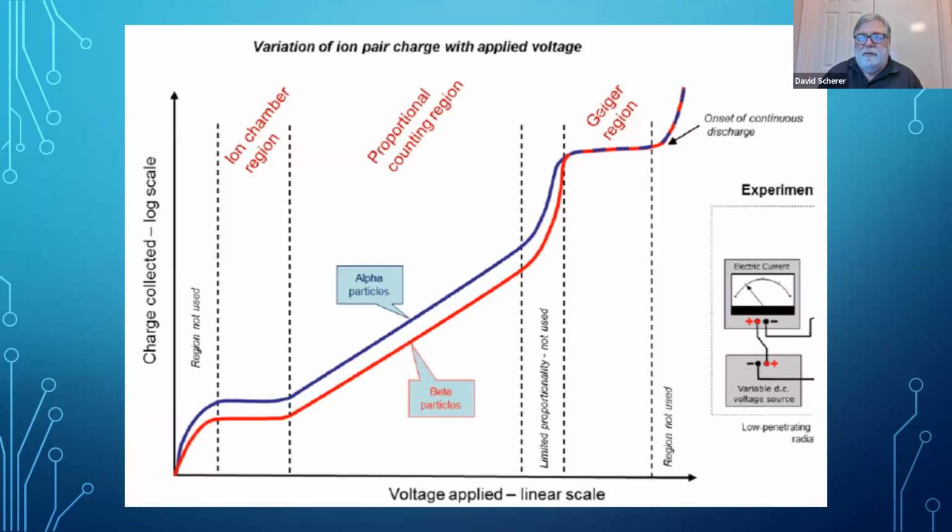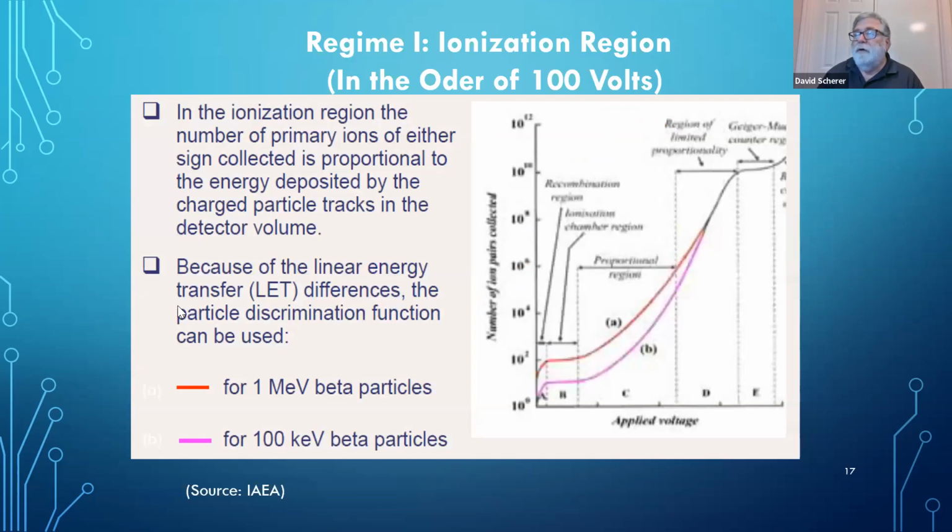The radiation energy that's deposited by a low energy photon is different than the energy deposited by a high energy photon, and you can see that in terms of the pulse height that's produced. The signal that's produced will be different for a low energy or a high energy radiation. Geiger counters are very rugged, very robust. Again, it's flat with voltage, so it's very good for field operations. It is useful for looking for contamination in particular, and not so much for measuring dose rate. Okay.